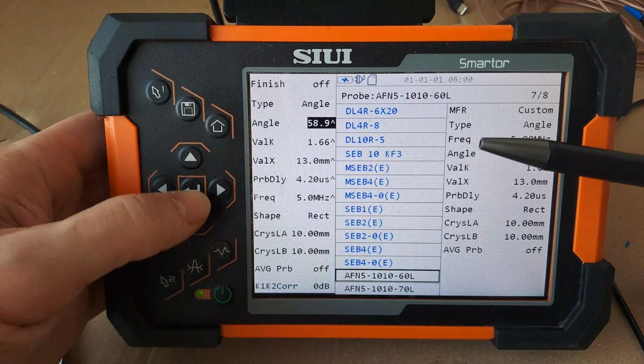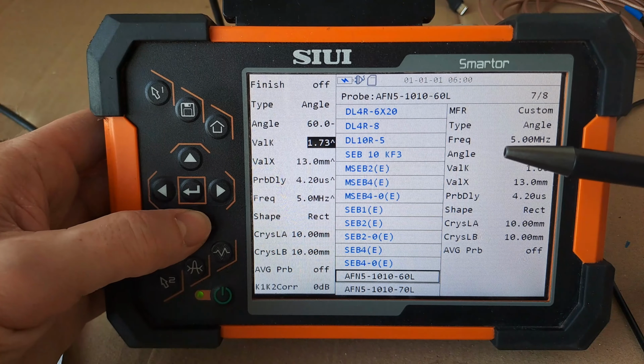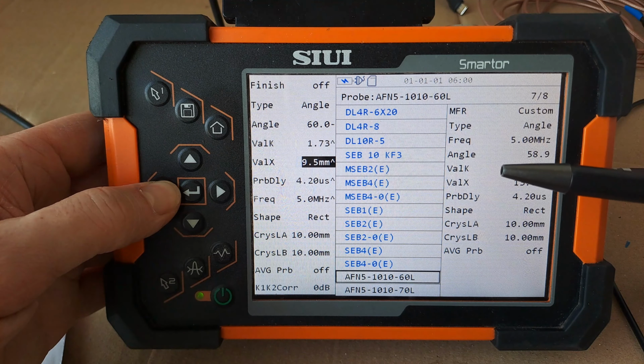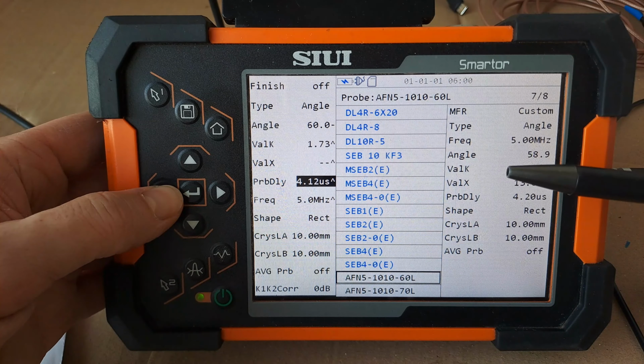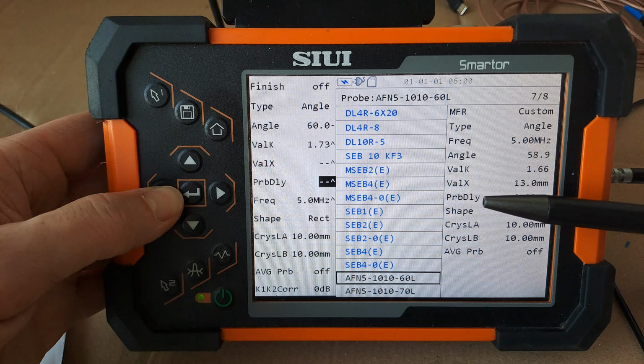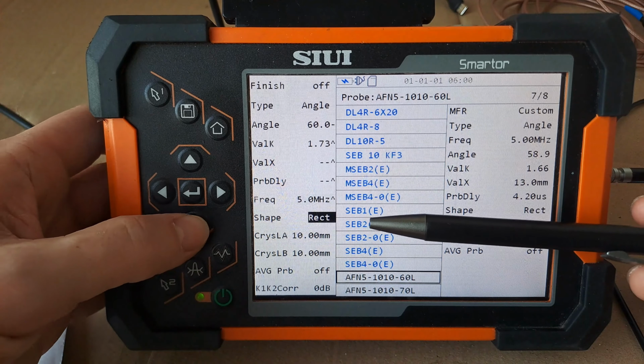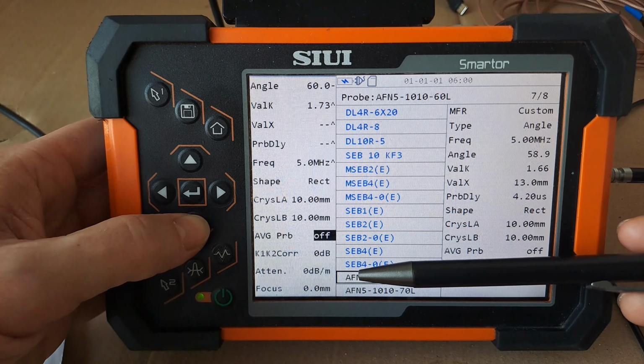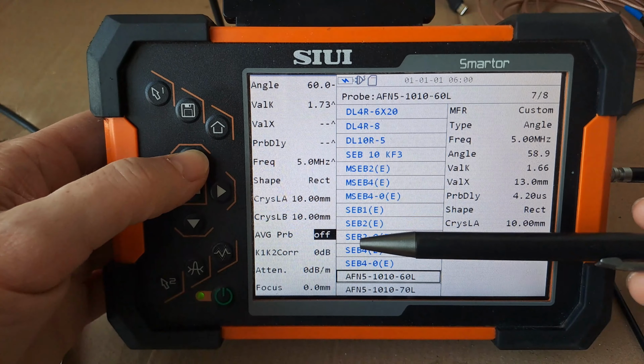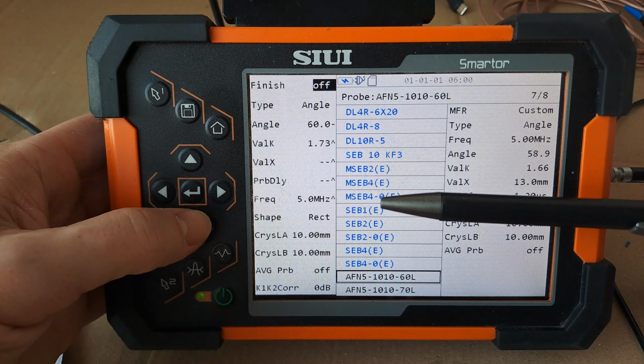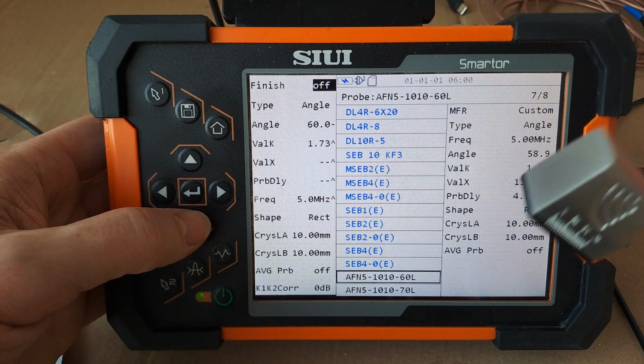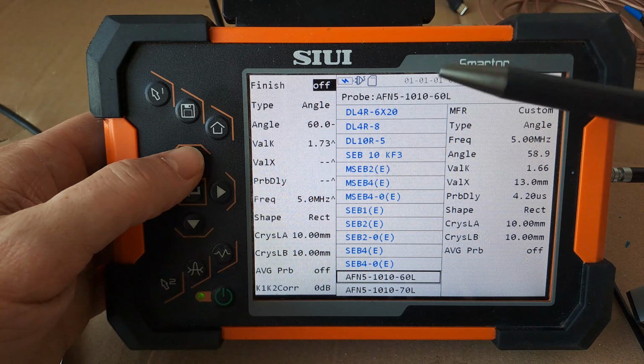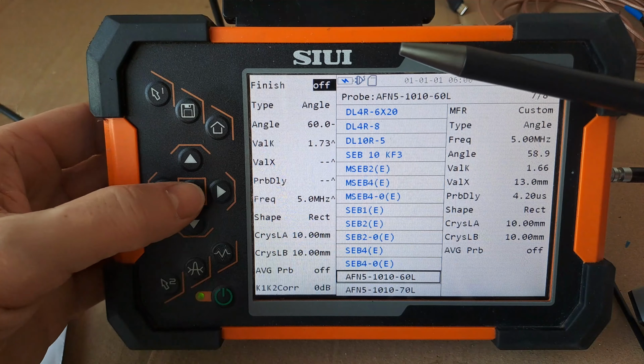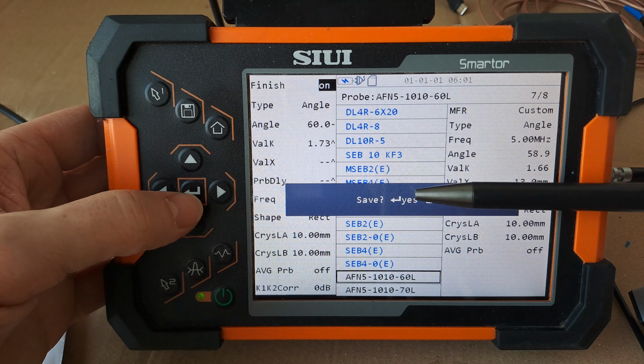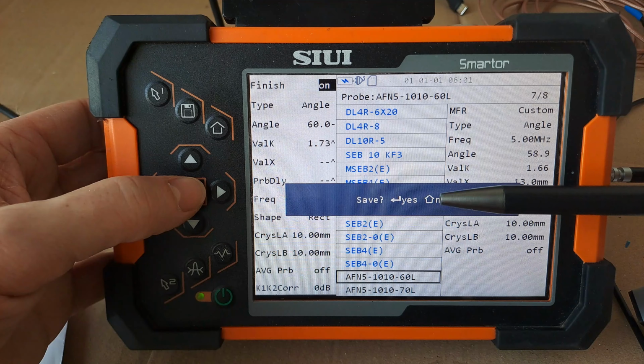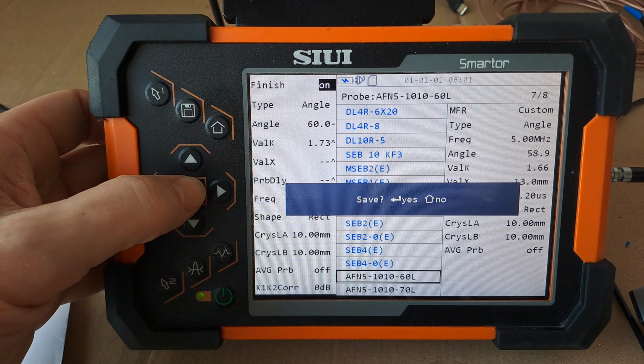So I go down and put the angle now, 60. Value X, I have no idea what it is, so I'm putting 0, probe delay 0. And then 5 megahertz, rectangular 10 by 10. Okay, so I have put all of the things. That's a new probe, let's say. I don't know what is inside. It's not calibrated. And I go on finish, off, and enter. Save yes, no. So if I want to save this one, no, home, I click yes.